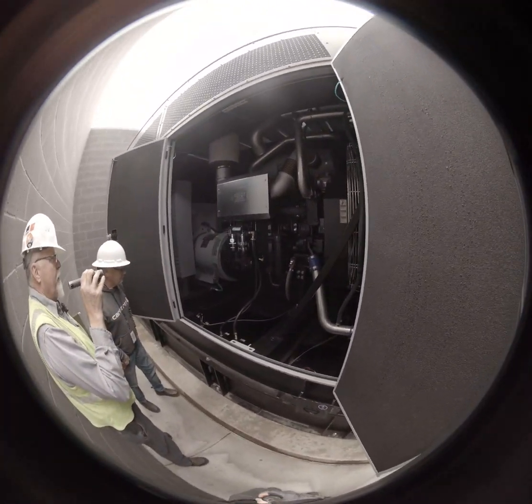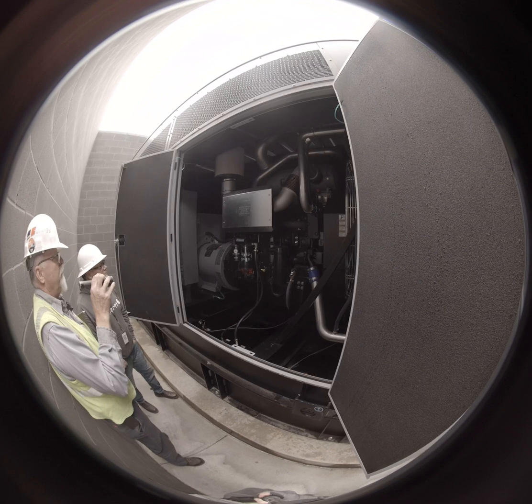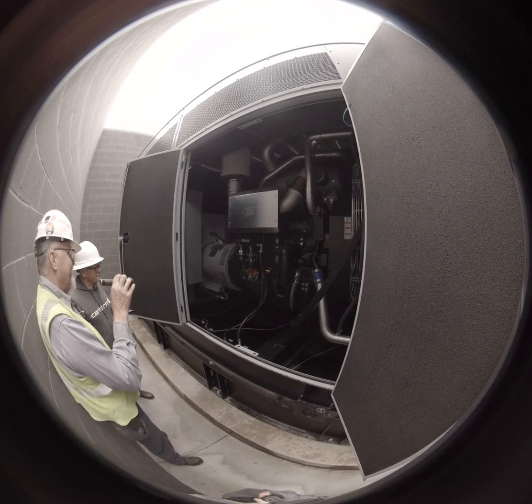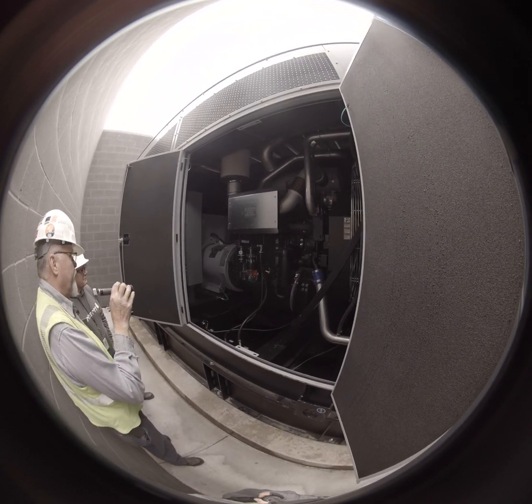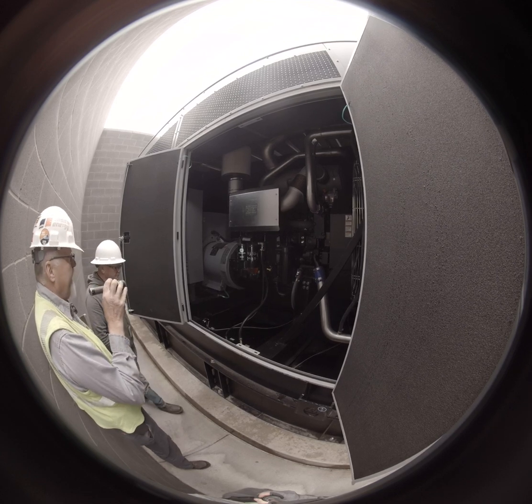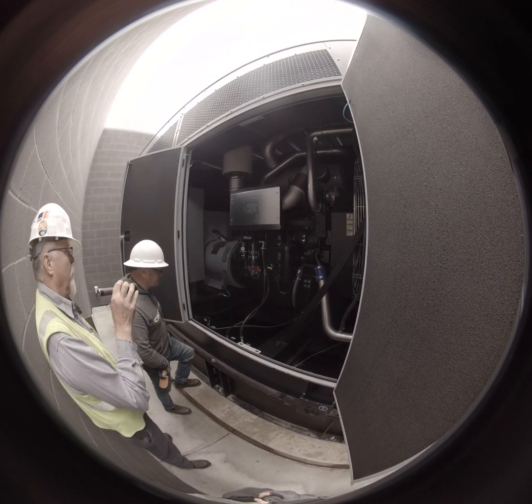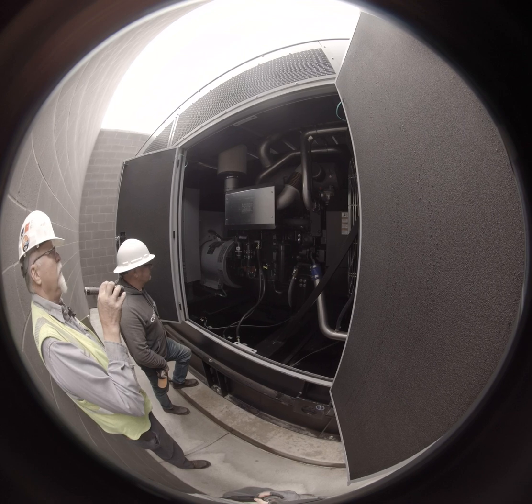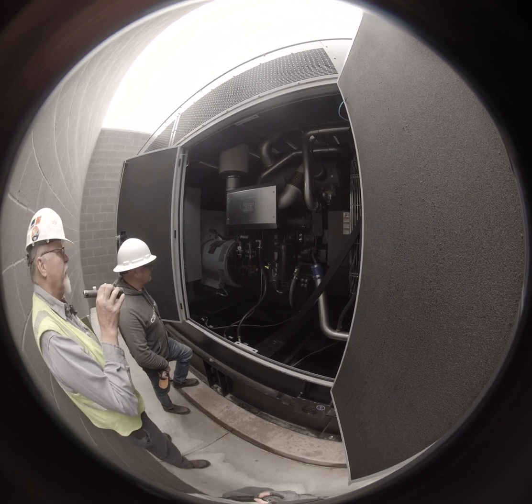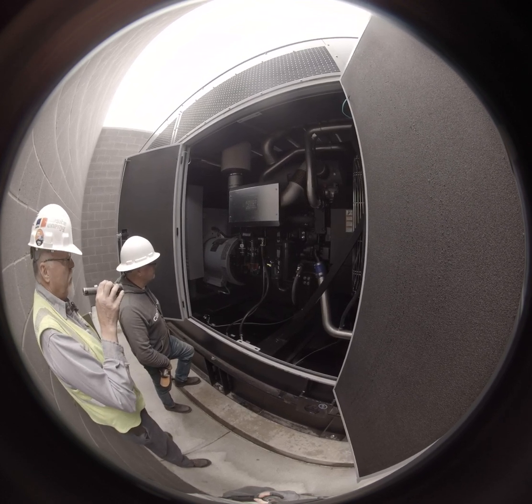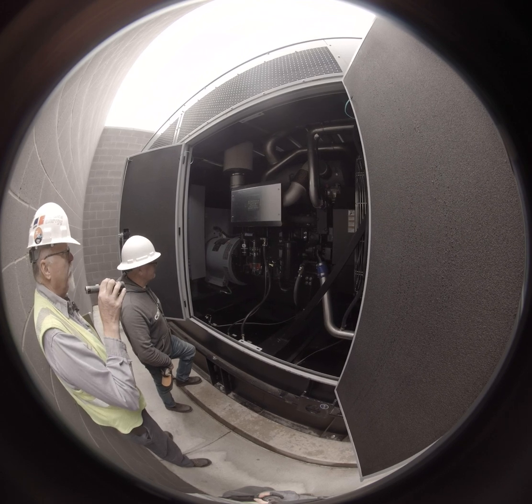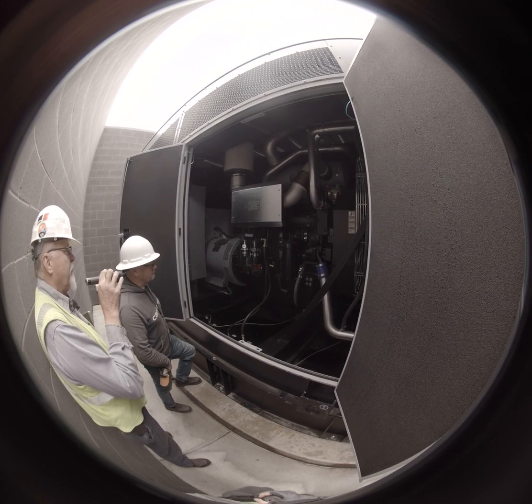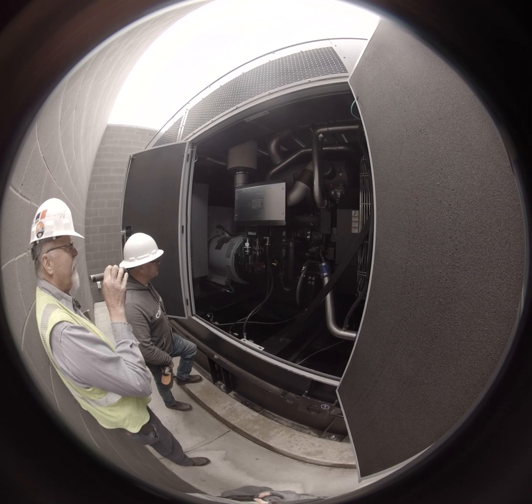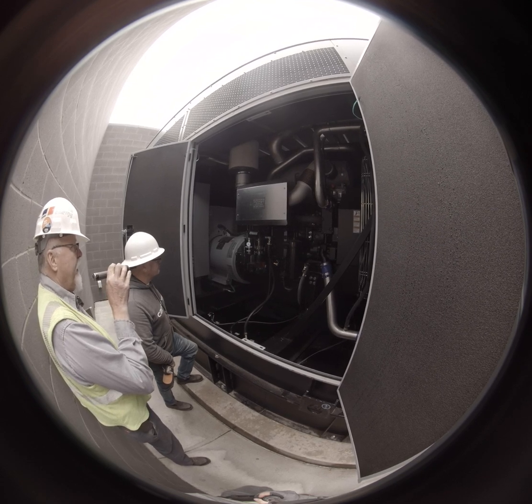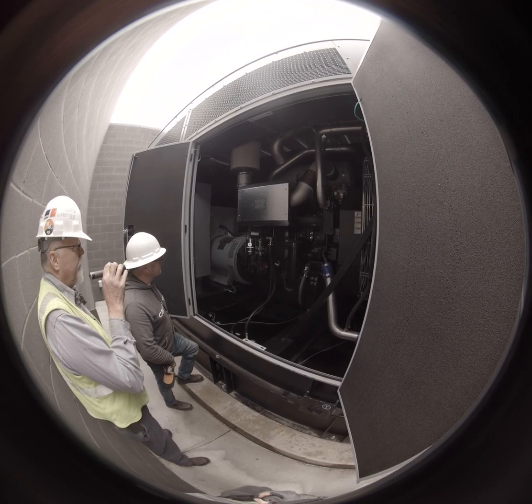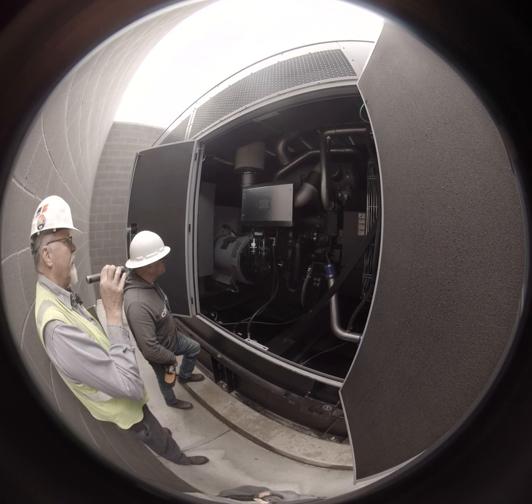So we have your primary water separator filter with a sensor on it. The sensor is for the water getting in or water sitting in the bottom of the bowl. And it will feed the ECU and tell it, and the ECU will tell the engine or the genset control that you have water in the fuel. Then we have our secondary fuel filter sitting left side there, and that is your 2 micron stripper to get all of the contaminants out of the fuel.